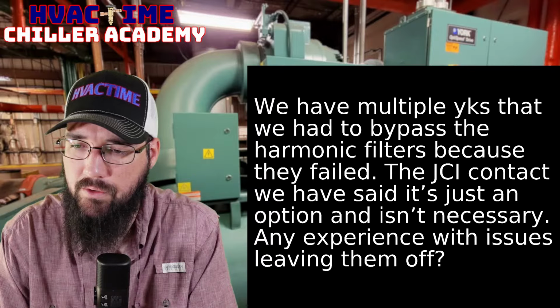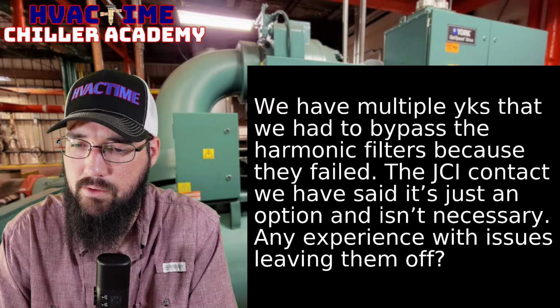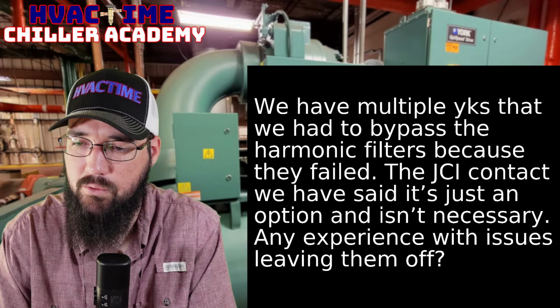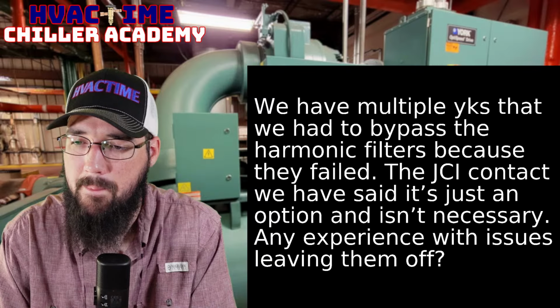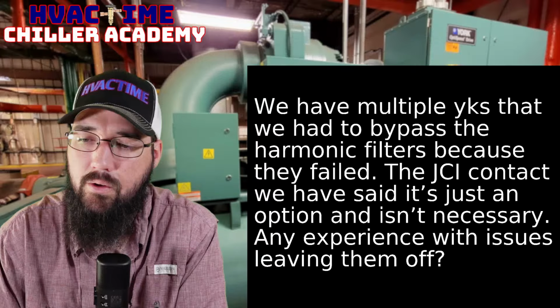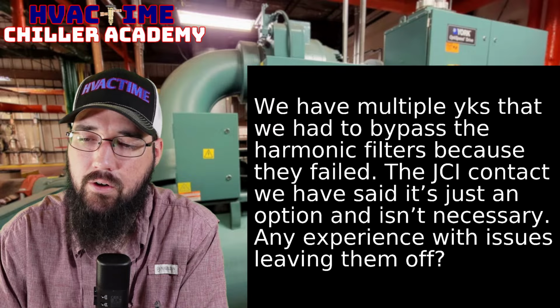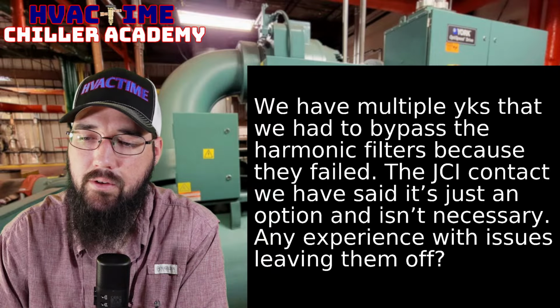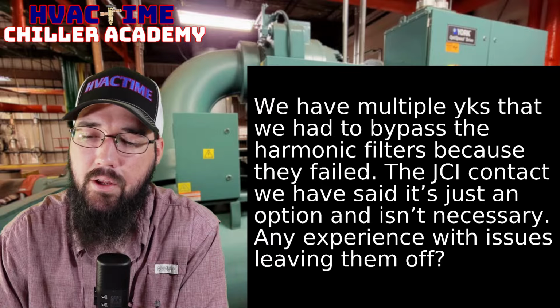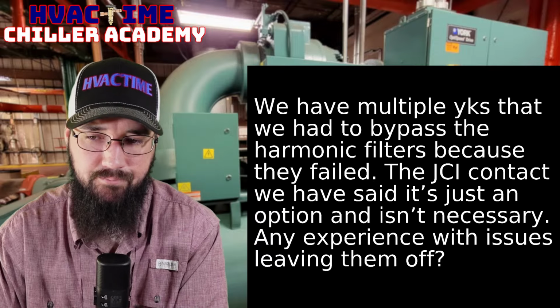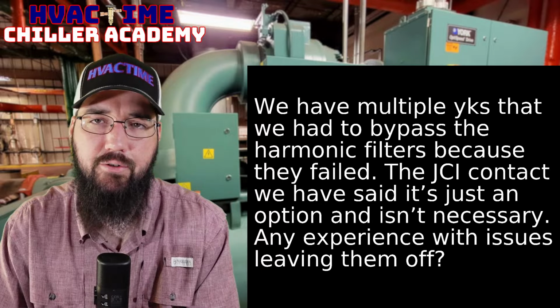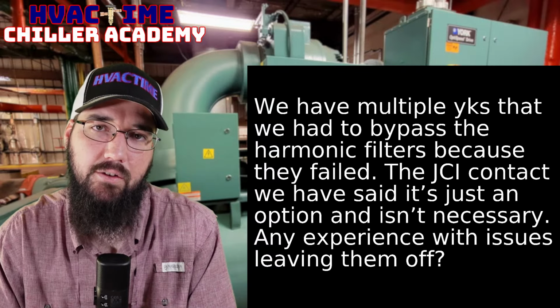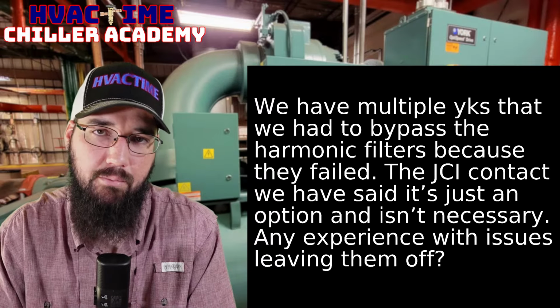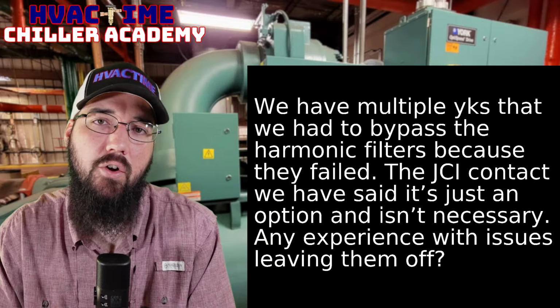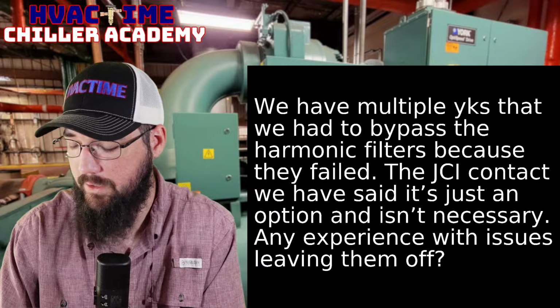Can't speak for certain on that, the line reactors weren't bypassed. It was an after hours situation, but seeing if it's worth looking into more as the YKs have been running fine. Okay, so the 19XR line reactor went out not long after bypassing that harmonic filter. So that's where I would look into that further, personally. Like I said, my main thing is just make sure that line reactor is in the circuit and it didn't get bypassed with the rest of the harmonic filter components. As long as that's in the circuit, then it is what it is, and you did the best you could.